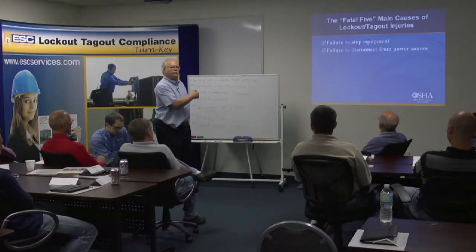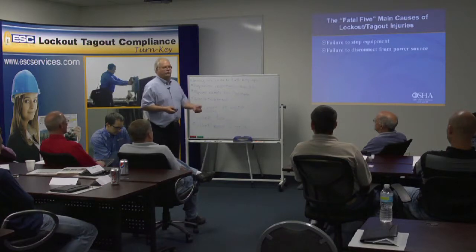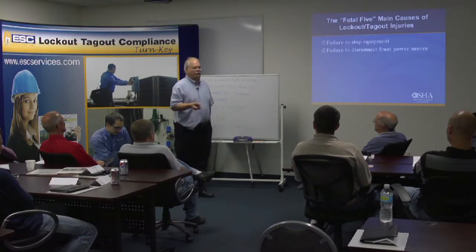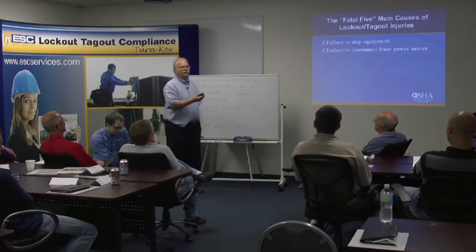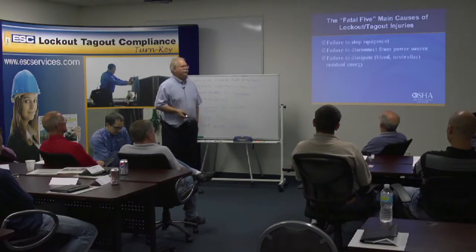I have a little Bostitch compressor I use for lockout training. I'll say: the cord is plugged in — what do I need to do? Unplug the cord. But what do I have in that air receiver? Compressed air. Many people miss that. And there's actually a spring inside on the valves that can spring. So you need to dissipate and bleed off that energy. That's part of the procedure.